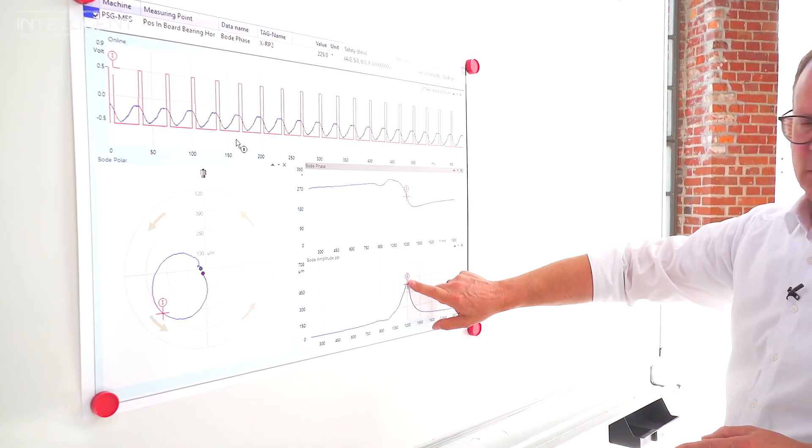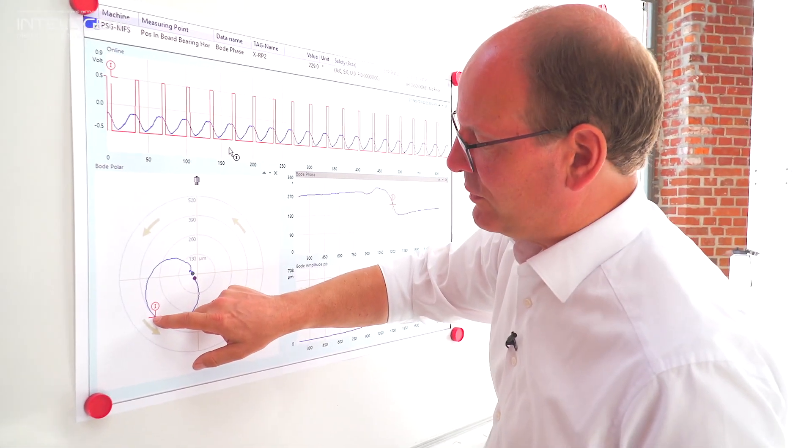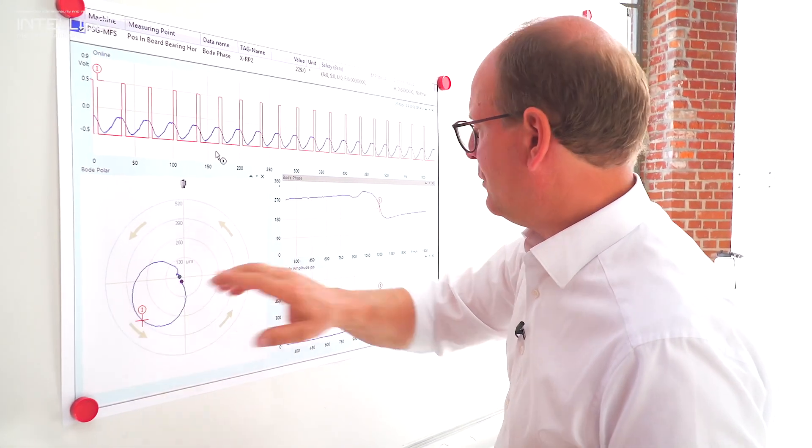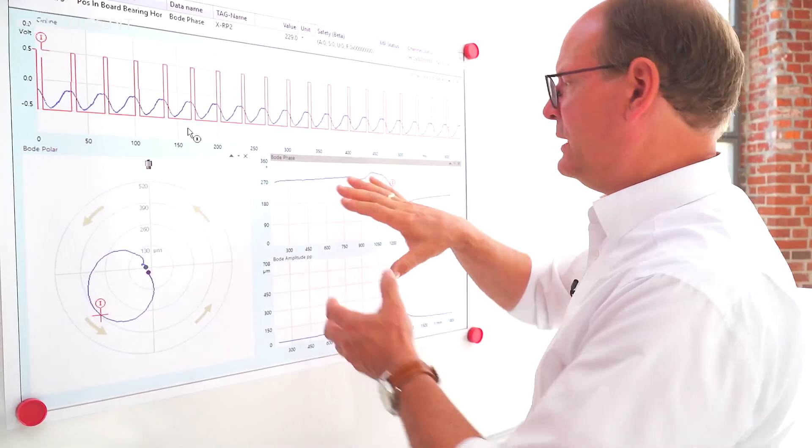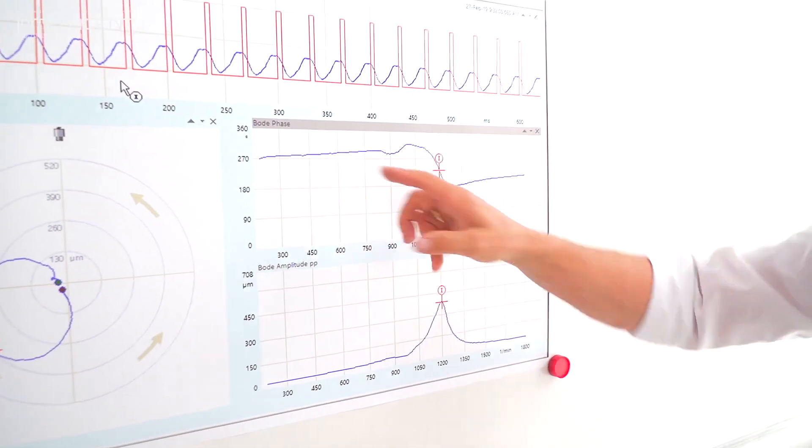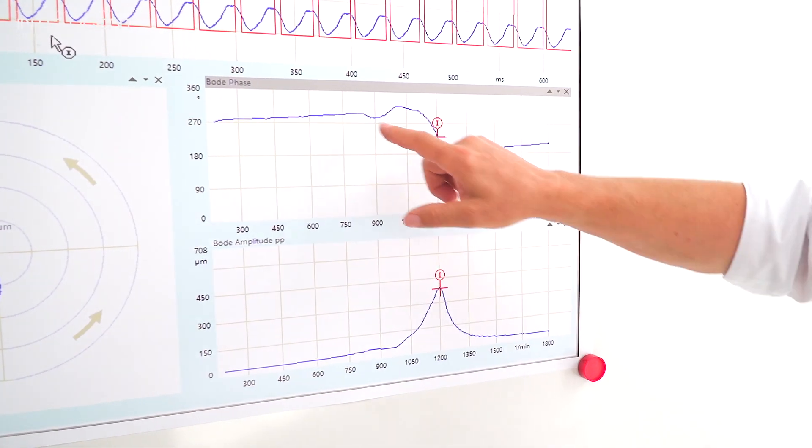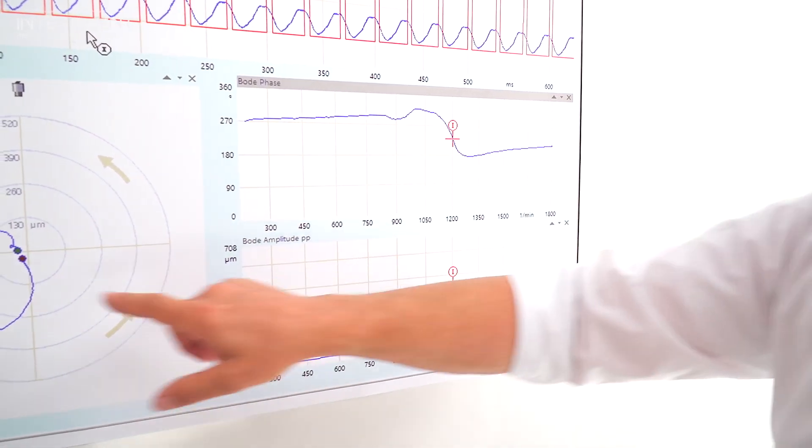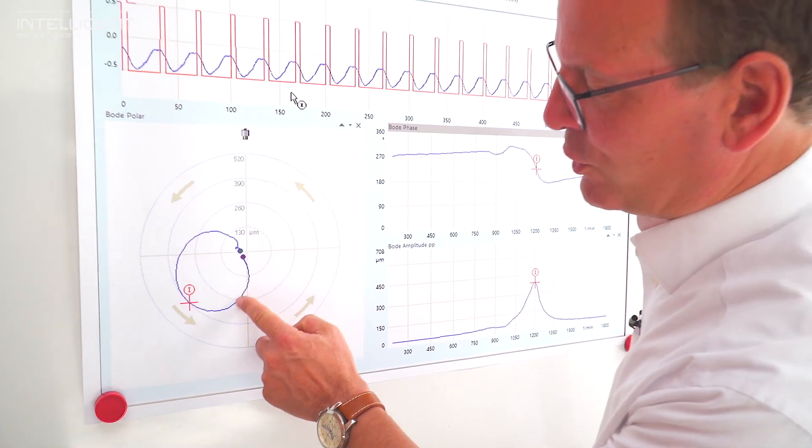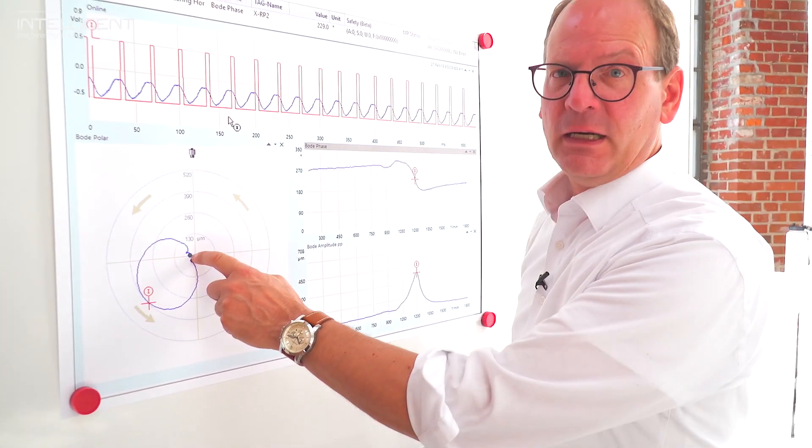This is when we reach the critical speed. Directly after reaching the critical speed by 180 degree we have a phase shift. That means we have a complete change of the phase coming in the other direction. That is what we see here. Here we have an increasing, then it's going back, and then we reach the final speed.